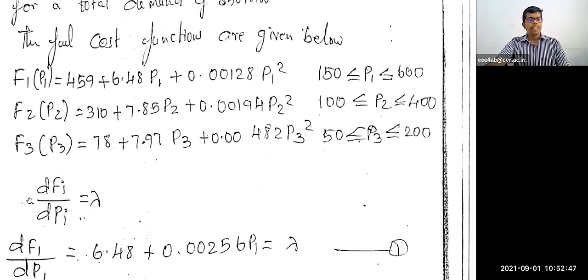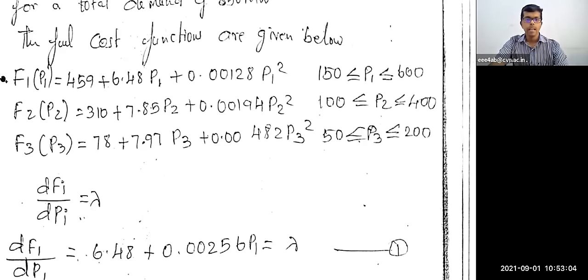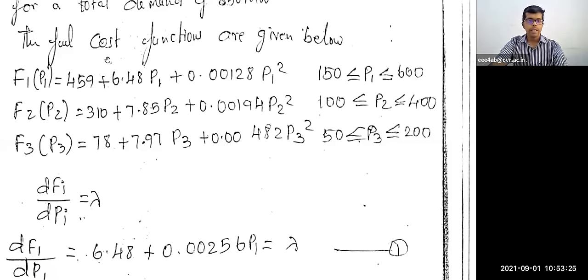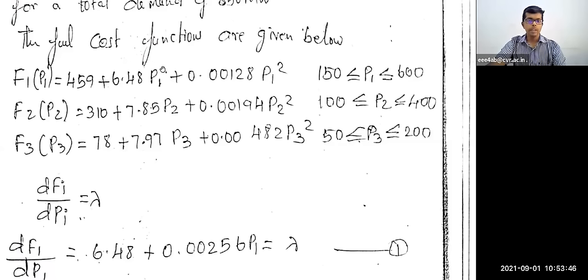Here you are seeing F1, F2 and F3 as fuel cost functions. In a previous problem, the heat rate H1 was given instead. If heat rate is given, you need to multiply by the fuel cost to get the fuel cost function: F1(P1) = H1 × fuel cost. Here, the fuel cost functions are directly given, so no conversion is needed. Be careful — if you solve using heat rate directly without multiplying the fuel cost, the demand will not be satisfied and your answer will be wrong.